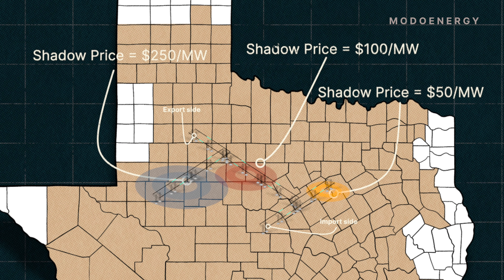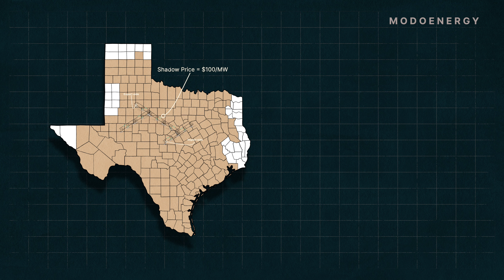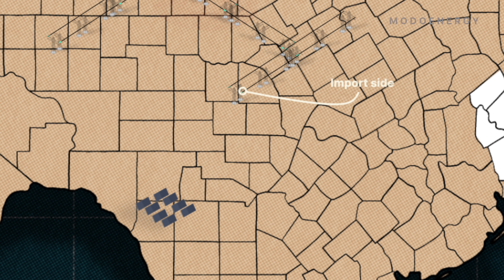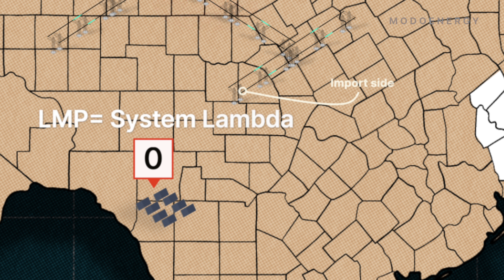Once there's a shadow price for every constraint on the system, ERCOT can then determine LMPs. Imagine for a moment that there's just a single congestion constraint in all of ERCOT. If a resource has no impact on the flow across that constraint — which tends to happen if it's located far from the congestion — then its shift factor will actually just be zero.